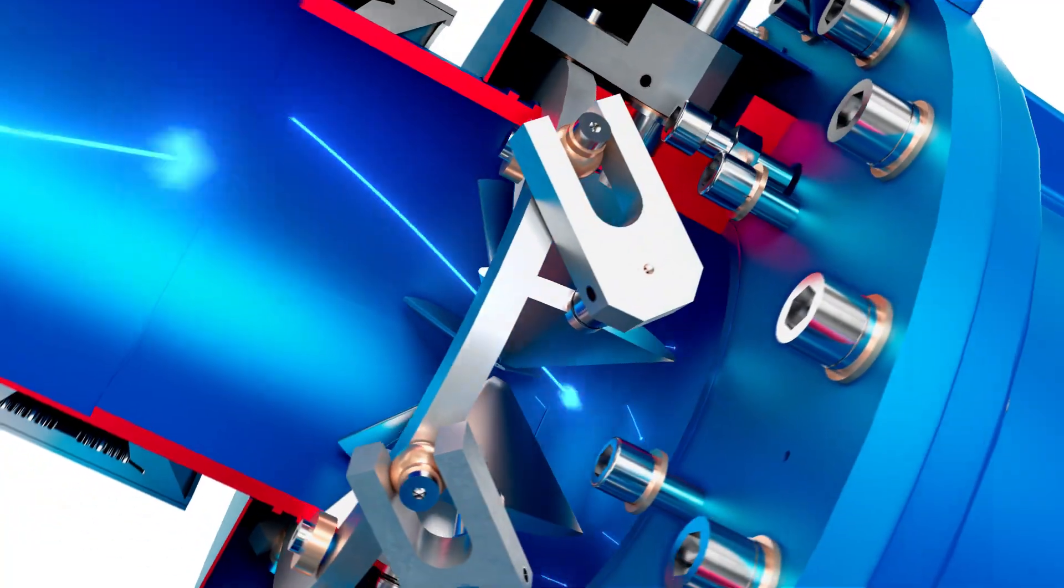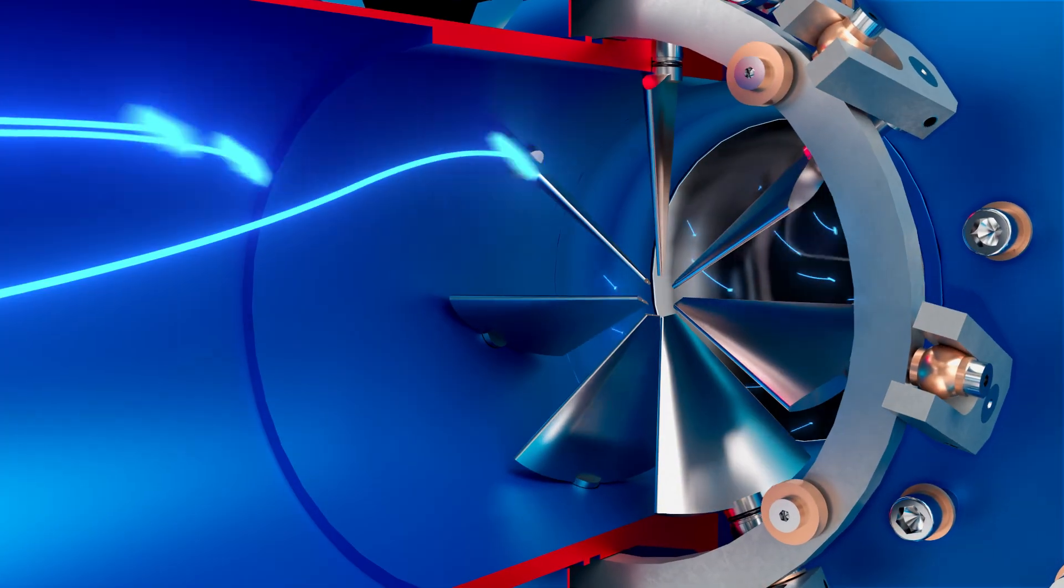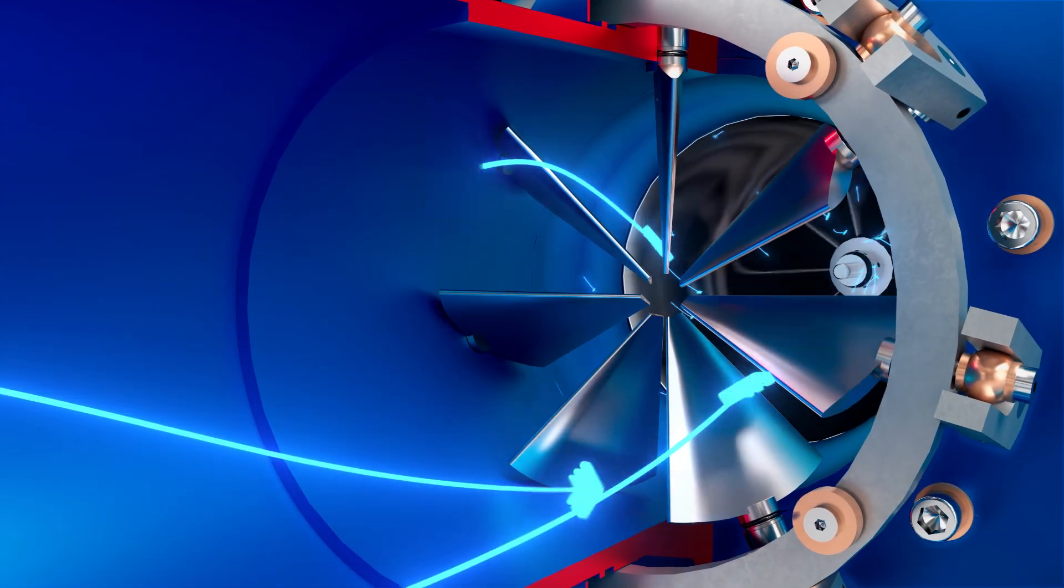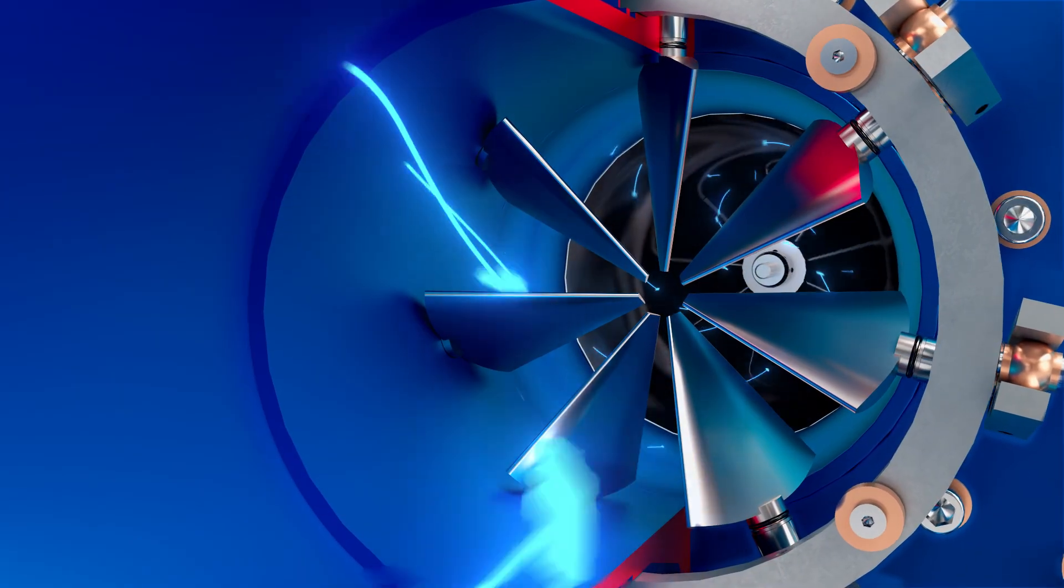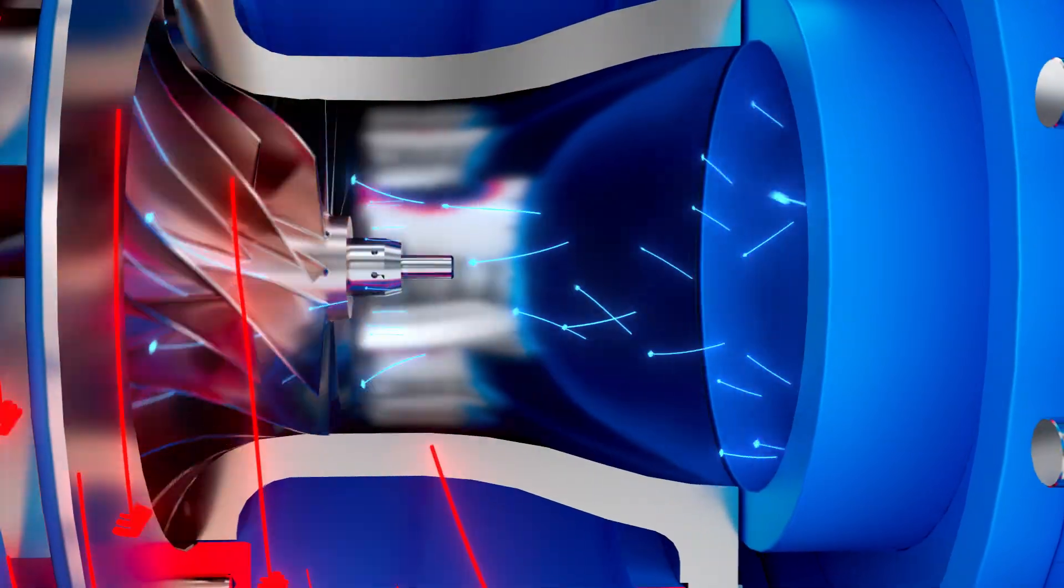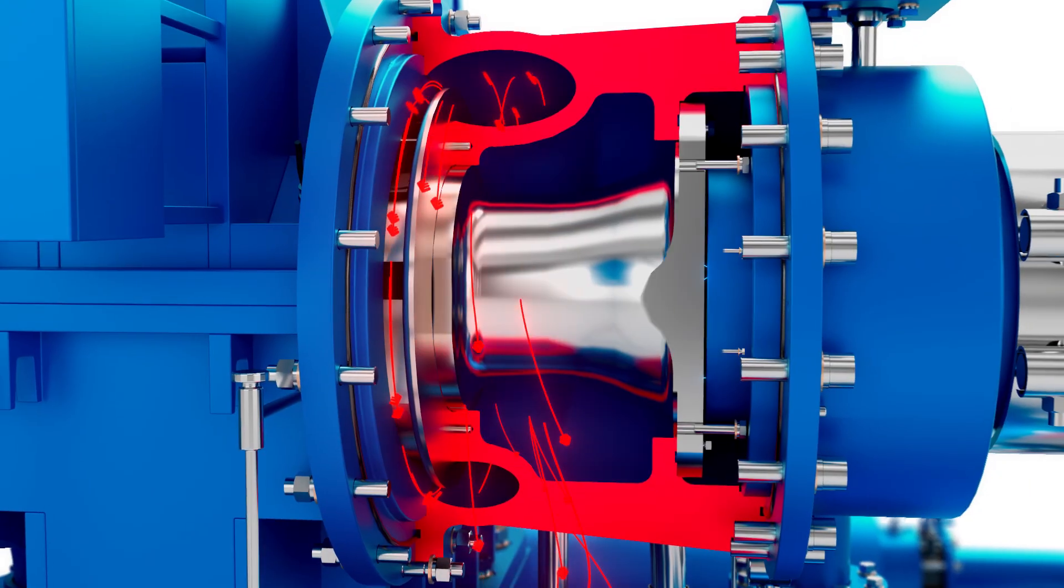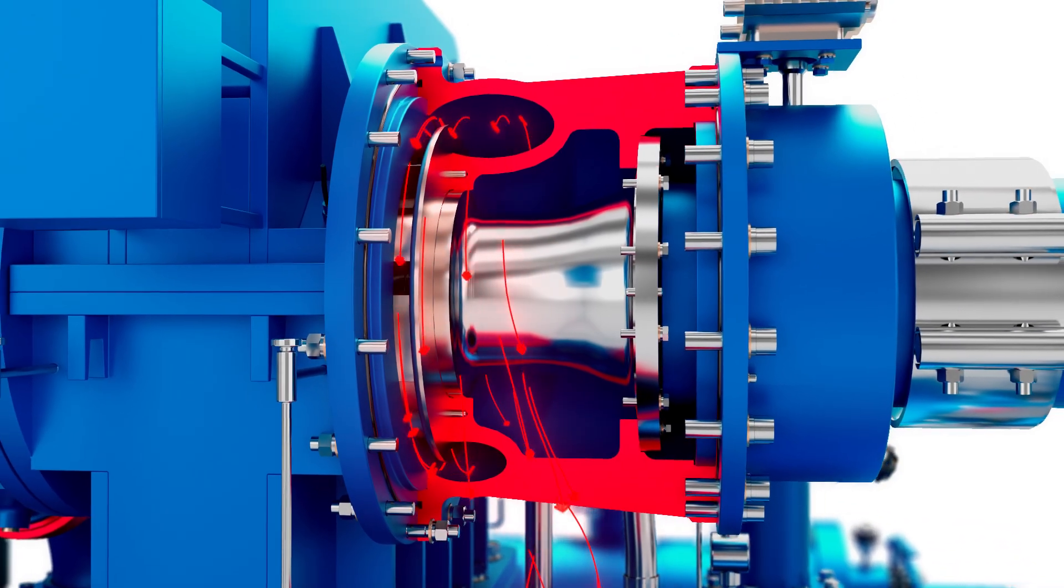The impellers draw in ambient air and accelerate it. As the air moves through the impeller, it gains velocity before reaching the diffuser vanes. When the high-speed air hits the diffuser vanes, it slows down, converting kinetic energy into pressure and heat.